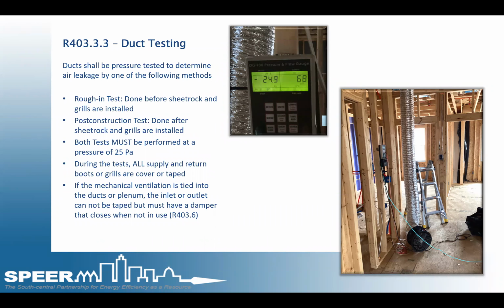During testing, all supply and return boots or grills should be covered or taped. If the fresh air, also known as mechanical ventilation, is tied into the duct system, or it dumps into a plenum, then the inlet or outlet cannot be taped. It must have a damper that closes during the testing. So that last one I deciphered from a few places in the code. R403.6 states that the mechanical ventilation must have an automatic or gravity damper, but nothing is mentioned in the testing procedures of duct testing on how it's to be sealed.